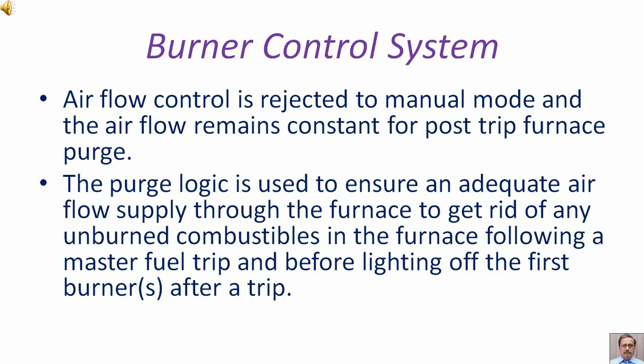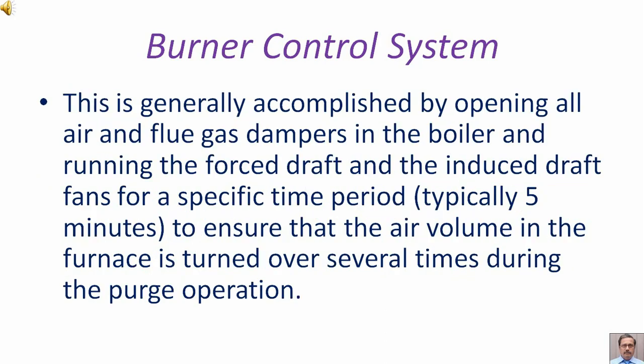Airflow control is rejected to manual mode and the airflow remains constant for post-trip furnace purges. The purge logic is used to ensure an adequate airflow supply through the furnace to get rid of any unburned combustibles in the furnace following a master fuel trip and before lighting of the first burner after a trip. This is generally accomplished by opening all air and flue gas dampers in the boiler and running the forced draft and the induced draft fans for a specific time period, typically 5 minutes, to ensure that the air volume in the furnace is turned over several times during the purge operation.